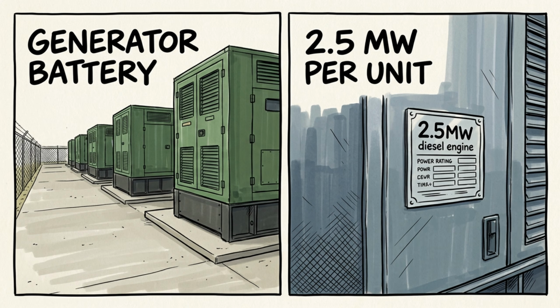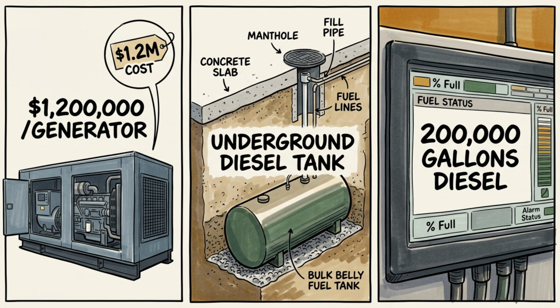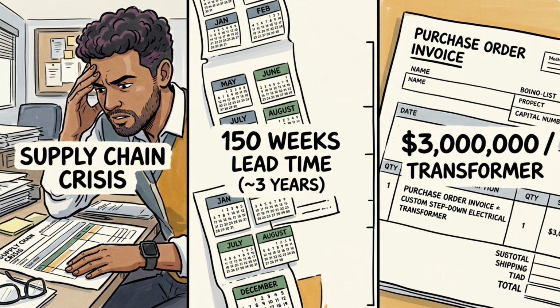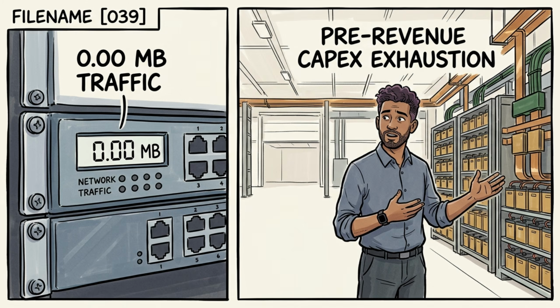And because your contract guarantees 99.999% uptime, known as 5 nines reliability, you have to line your concrete yard with a battery of 2.5 megawatt diesel generators, each costing over $1 million, supported by fuel tanks holding hundreds of thousands of gallons of diesel fuel. To make matters worse, custom high-voltage transformers now take up to 150 weeks to deliver at $3 million apiece. Before a single megabyte of data crosses your threshold, you will spend more on backup batteries and copper wiring than most companies spend in their entire operational lifetime.